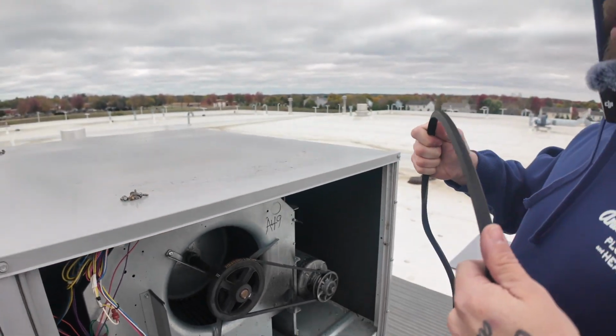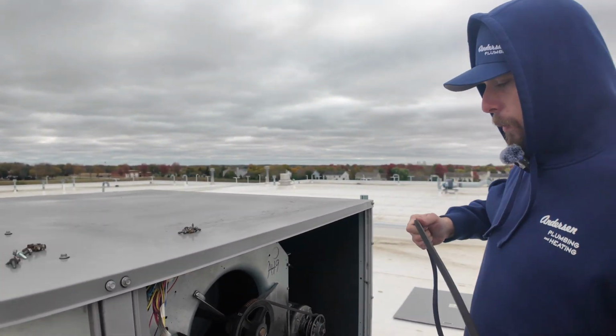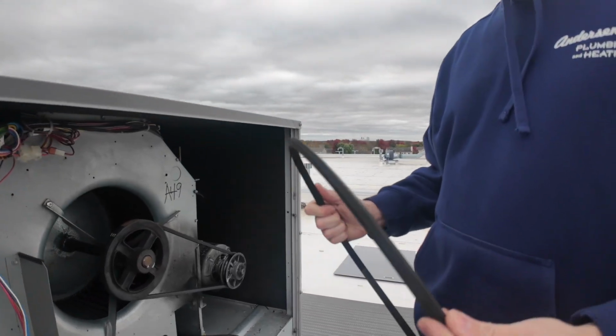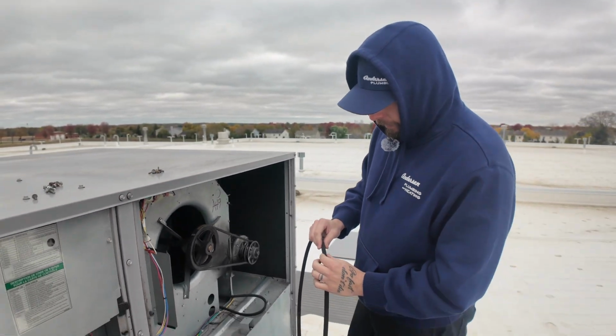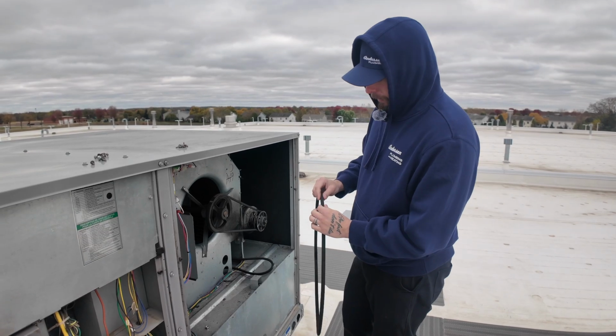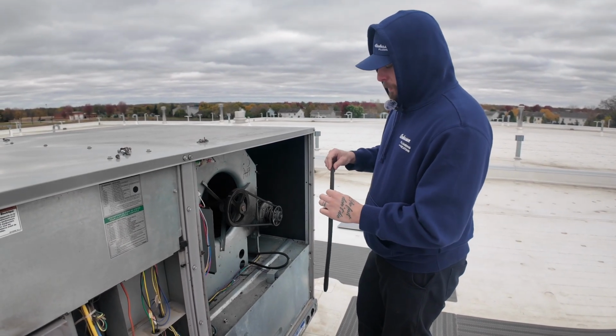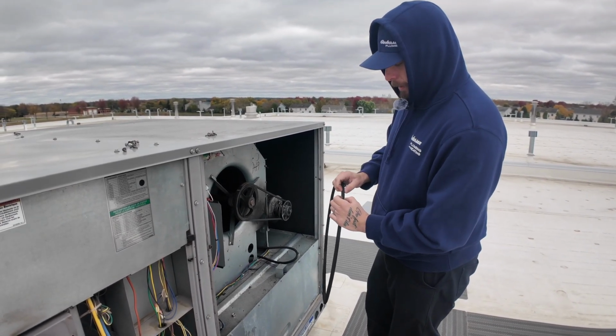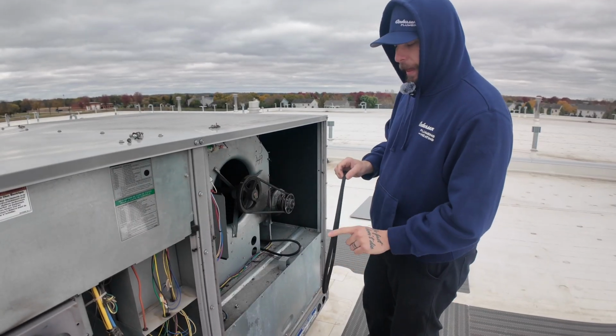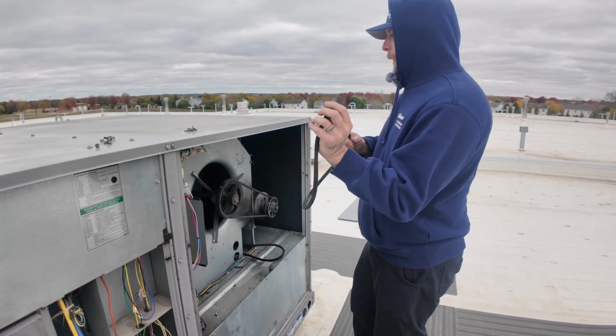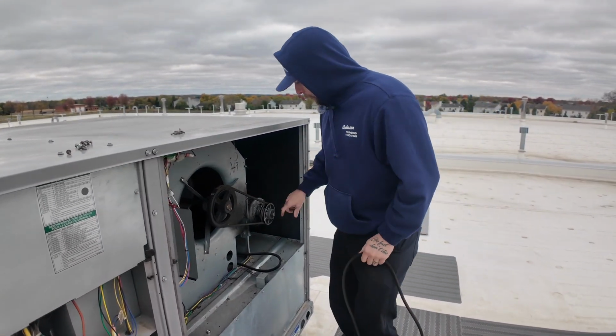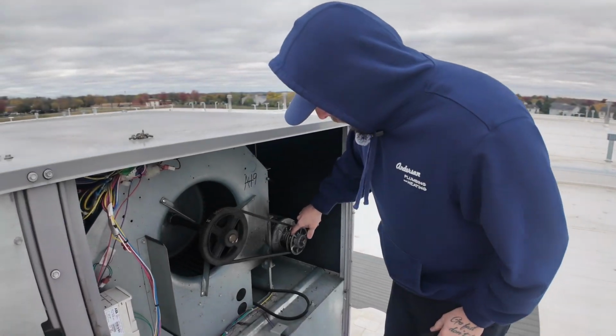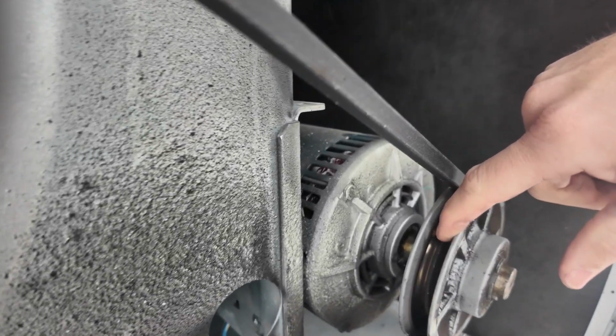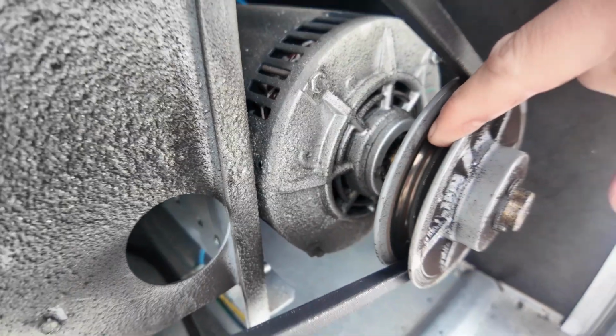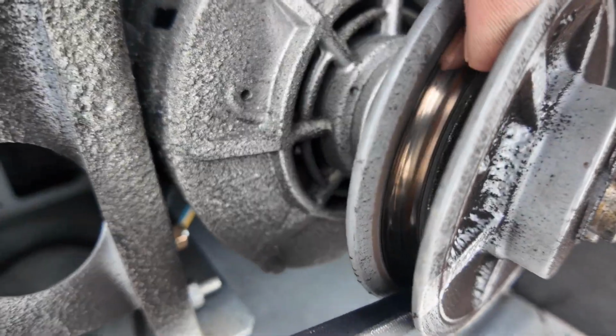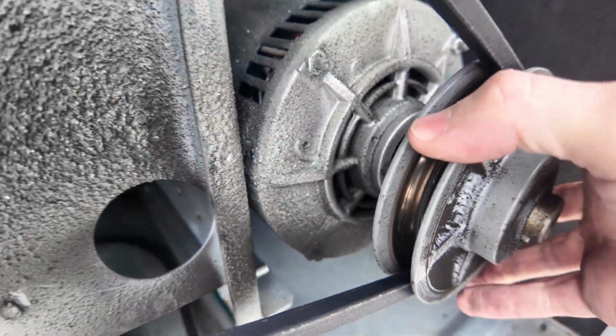when it comes to actually driving a motor with this style of system, it's called a V-drive. Now, this belt has a taper to it. What drives this belt is actually the sides of the belt, not the flat part in the center. So what happens over time is, if you look at this pulley, it's pretty worn out. There's a pretty heavy groove in the side of it. It might be a little hard to pick up on camera, but this pulley needs to be replaced.